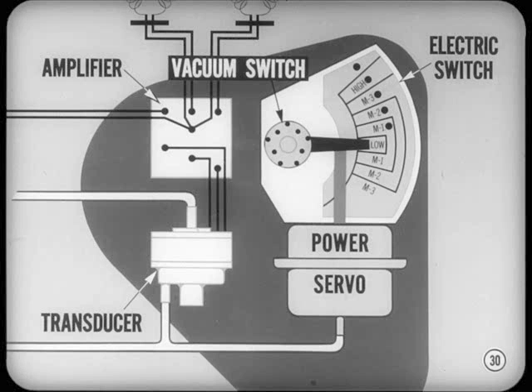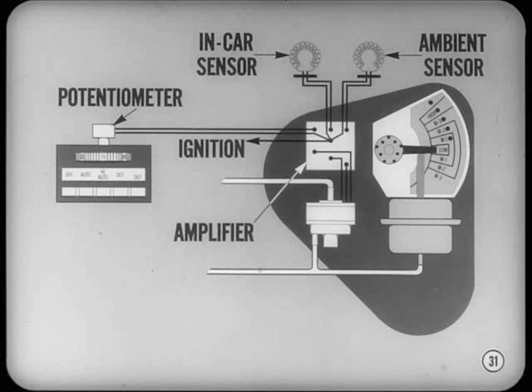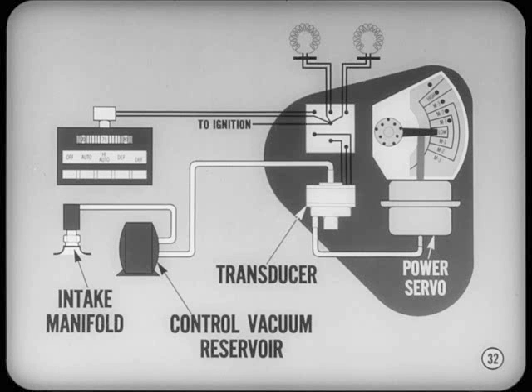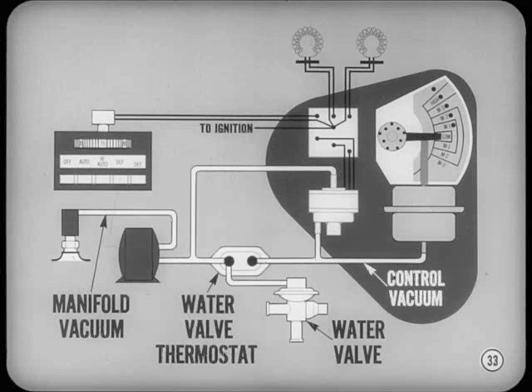Okay, Tech. This drawing represents the control unit assembly and identifies the amplifier, the transducer, and the power servo. On the left side of the power servo is the rotary vacuum switch mechanism, and the electric blower speed switching setup is at the right. Here we've added the in-car sensor, the potentiometer unit, and the ambient sensor connections to the amplifier. Notice that these units are all connected to an ignition circuit terminal in the amplifier so that the electrical part of the control circuit is live when the ignition is on. In this illustration, the vacuum connection to the intake manifold, the control vacuum reservoir, the manifold vacuum line to the transducer, and the control vacuum connection between the transducer and the power servo have been added. Next, the water valve and the water valve thermostat have been added and connected into the control vacuum circuit.